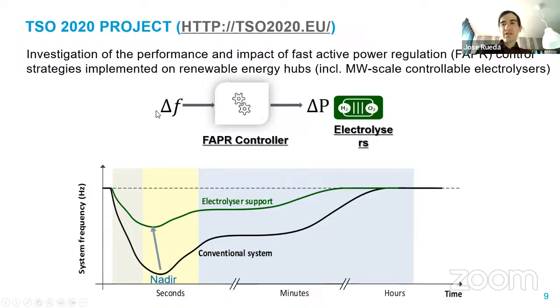Most appliances here in Europe run at 50 hertz, the same frequency. When there's an imbalance between generation, consumption, and losses, this frequency starts to vary, as in this example figure. If there is less generation of electrical energy than consumption, frequency will tend to decrease. Without conventional plants to stabilize it, this will go very steeply to unacceptable values. At this point, the maximum frequency deviation downward, the system will trigger protection devices.